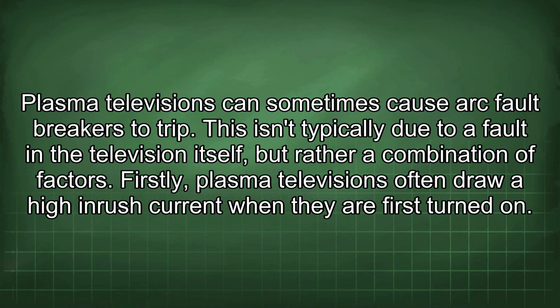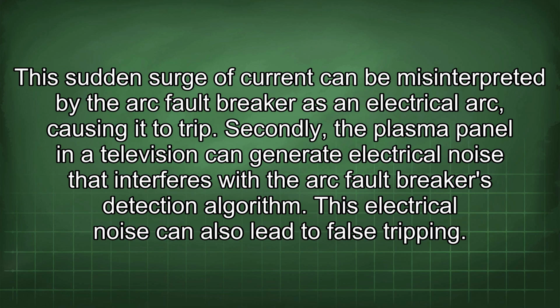Plasma televisions can sometimes cause arc fault breakers to trip. This isn't typically due to a fault in the television itself, but rather a combination of factors. Firstly, plasma televisions often draw a high inrush current when they are first turned on. This sudden surge of current can be misinterpreted by the arc fault breaker as an electrical arc, causing it to trip. Secondly, the plasma panel in a television can generate electrical noise that interferes with the arc fault breaker's detection algorithm. This electrical noise can also lead to false tripping.